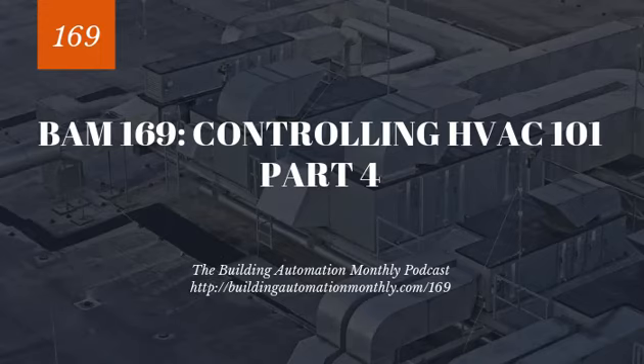Now, like I said, this assumes that the boilers are the same size and that you have the same flow rate through the boilers. There is a hybrid version of this where they're set to maintain a supply set point, and then they vary their own firing rate based on the supply temp. And this can be used when boilers are different sizes, with different capabilities of heat production. But this is Unison Control. It's one of my favorite controls. It's very simple to do.